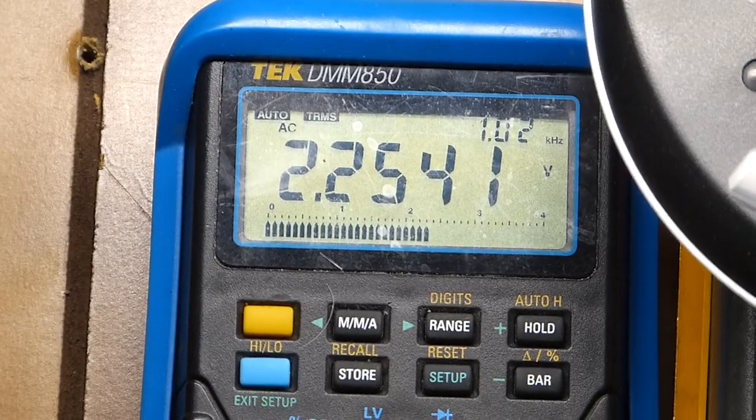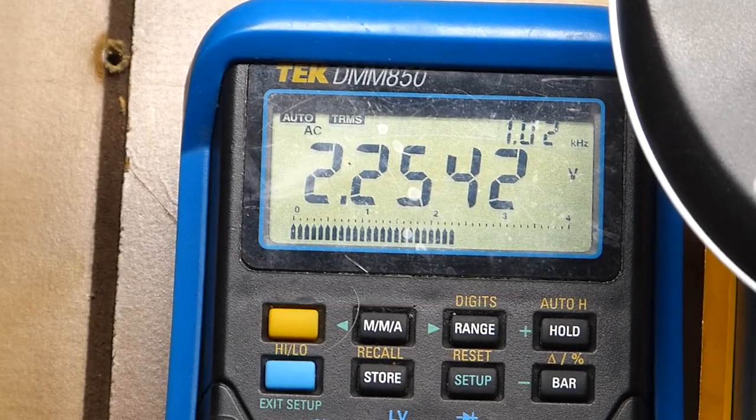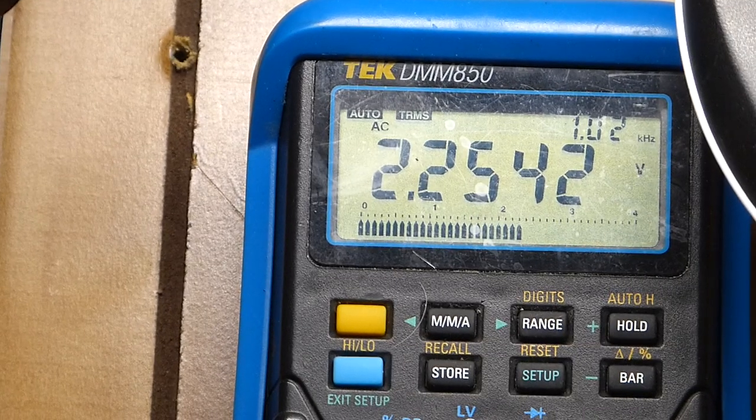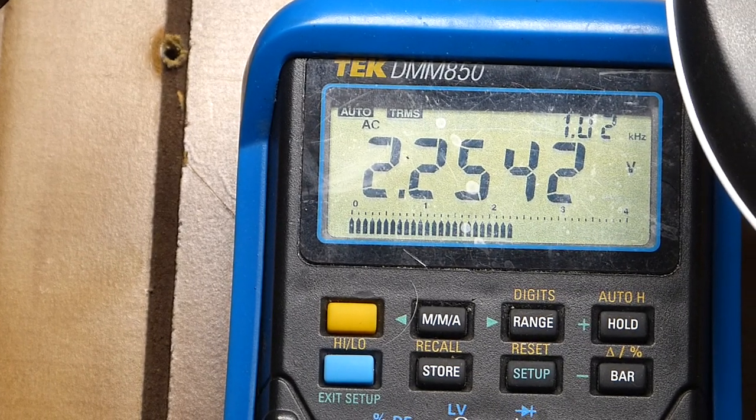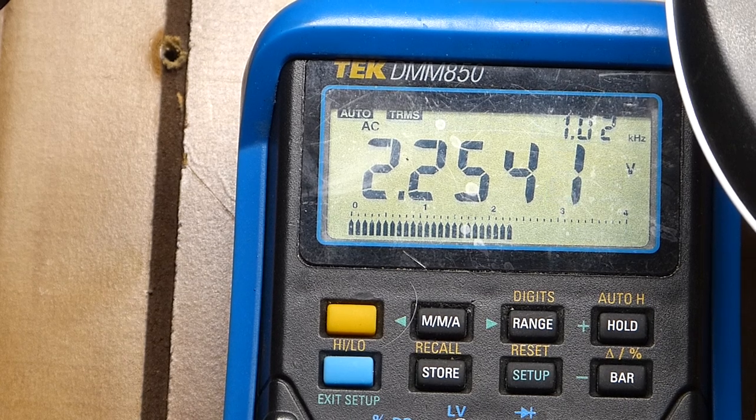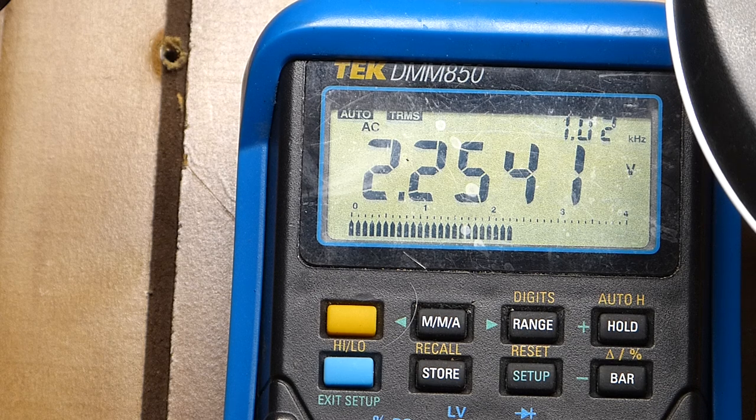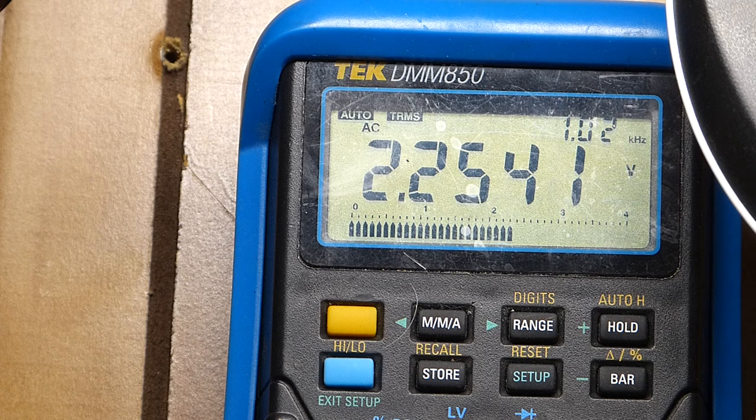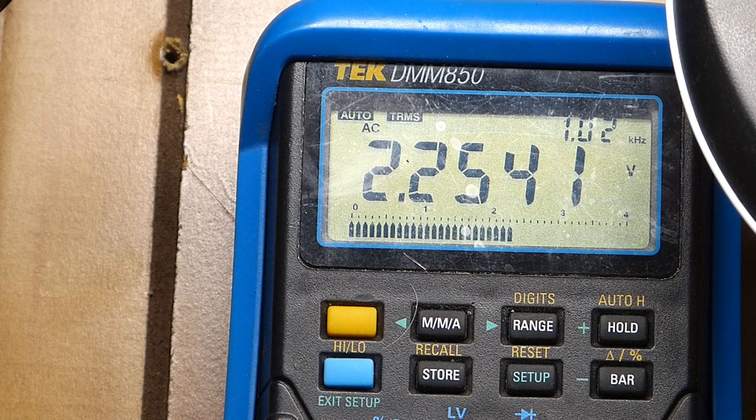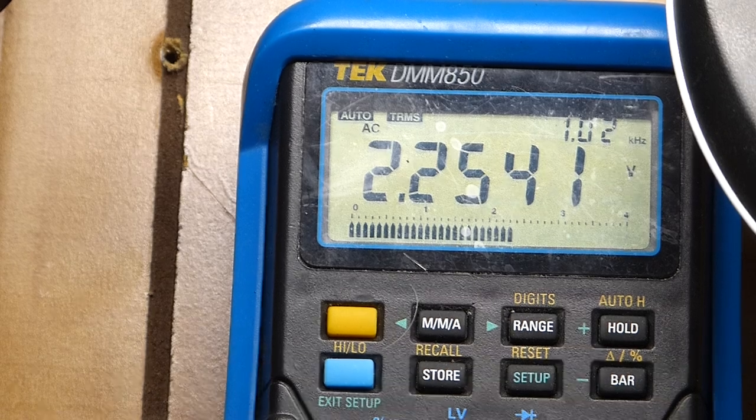So we're just measuring the current through it by clamping a meter to it. We're also going to measure the voltage across it so we know what we're doing. So we're going to put a very accurate voltmeter across it. Now I've got the cutest little HP AC meter. You've got to see it measures all the way down to the one millivolt full scale. So we've got some voltage flowing through it. We've got some current and all that kind of stuff. And here's our voltage right here. Let's look at the voltage and I'll show you. The voltage is right there. We're going to zoom right in so you can see very clearly. 2.2541.